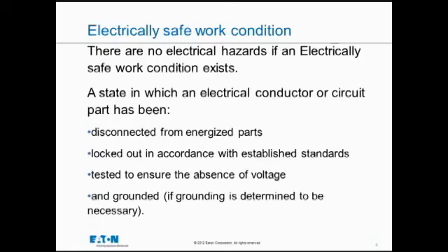So if you remove the electricity from a workplace, there is no electrical hazard. That's more or less an understood thing. If there's no electricity there, then you don't have a hazard. And there's a step-by-step procedure. More or less, we use the word lockout tagout in a lot of cases to get to what's called an electrically safe work condition. You know, open the circuit up, make sure your lock's on correctly, make sure there's no voltage there. You know how to use your voltage tester, and then if you need to, you put on temporary grounding.